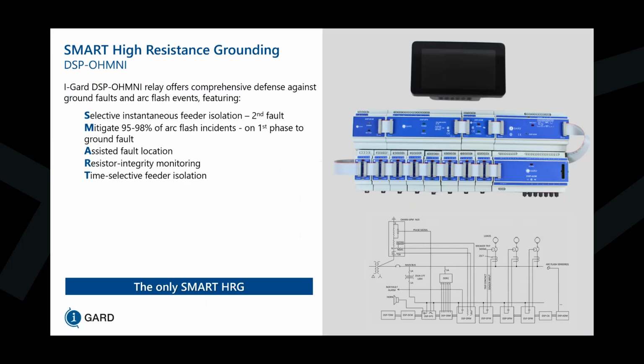So our DSP system is a very unique solution involving advanced high resistance grounding. So this is not your standard high resistance grounding relay. It has various capabilities in monitoring the resistor, monitoring voltage between phase to ground. It also monitors individual feeders for ground fault pickup. It has second ground fault protection. And we've also included an arc flash module which can connect to up to 21 sensors across 7 channels, three sensors per channel. We can use fiber optic sensors or pressure sensors to connect to this relay module, and this would be useful within the switchgear that the CTs and the feeder connections are connected to.